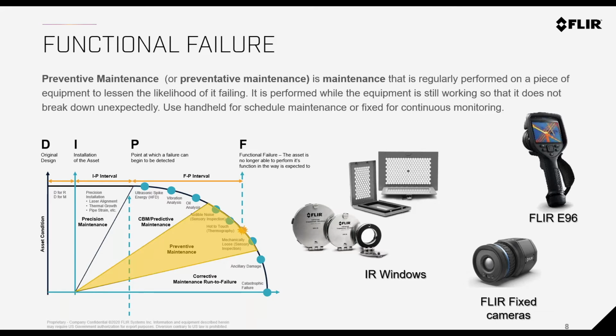The way we use thermal imaging for motors and equipment: if a piece of equipment heats up or cools down abnormally — a heat anomaly — you know something is wrong. It's supposed to be 80 degrees Fahrenheit and it spikes to 125 degrees Fahrenheit — you know something's wrong. You don't want that to go undiagnosed or let the equipment keep running at that heat. With a thermal imaging camera you can pick that up and get the right people out to do maintenance so you don't lose that equipment.